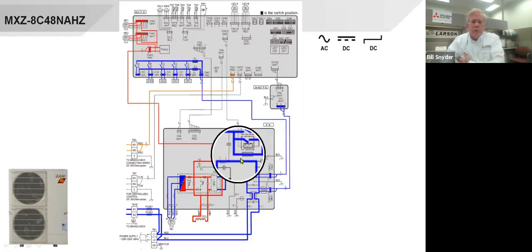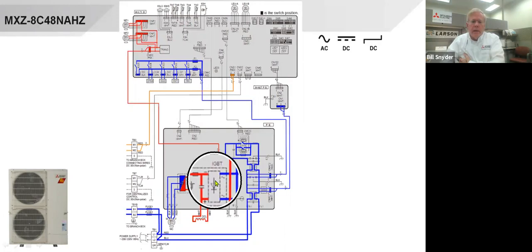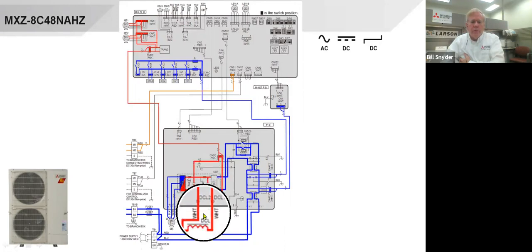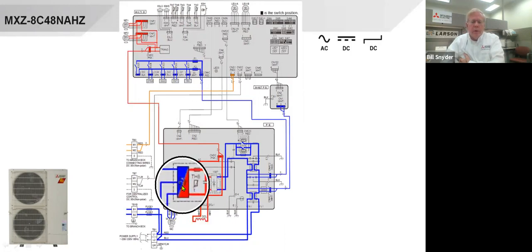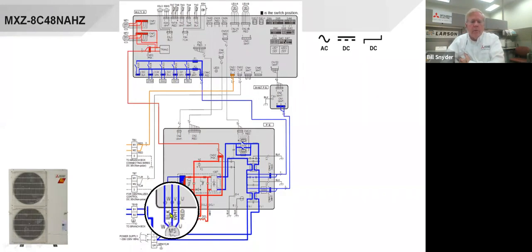Internally, this works the same. We go through here, we go through the IGBT and it converts it from AC volts to DC voltage, about 300 DC. We go through a reactor here to help clean up that voltage. And then we go over here to the inverter circuit and we take that DC voltage and we go back to U, V, and W. It's like a three-phase signal to the compressor, which again is labeled as a three-phase compressor, MC for motor compressor.